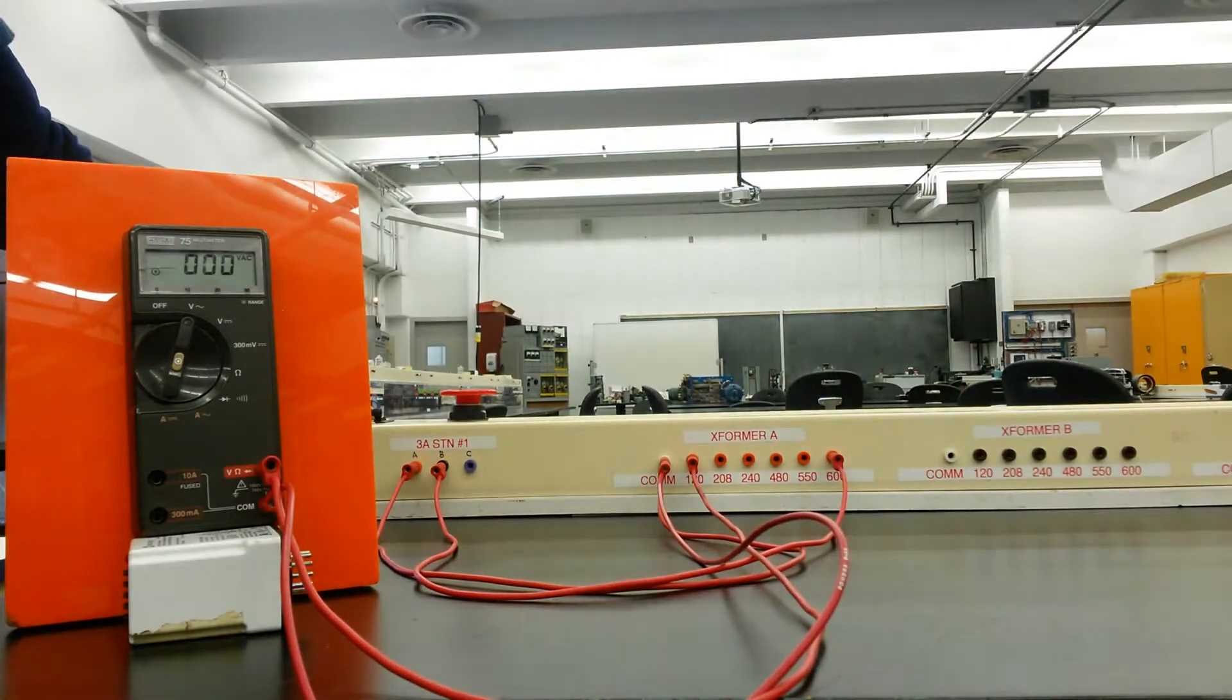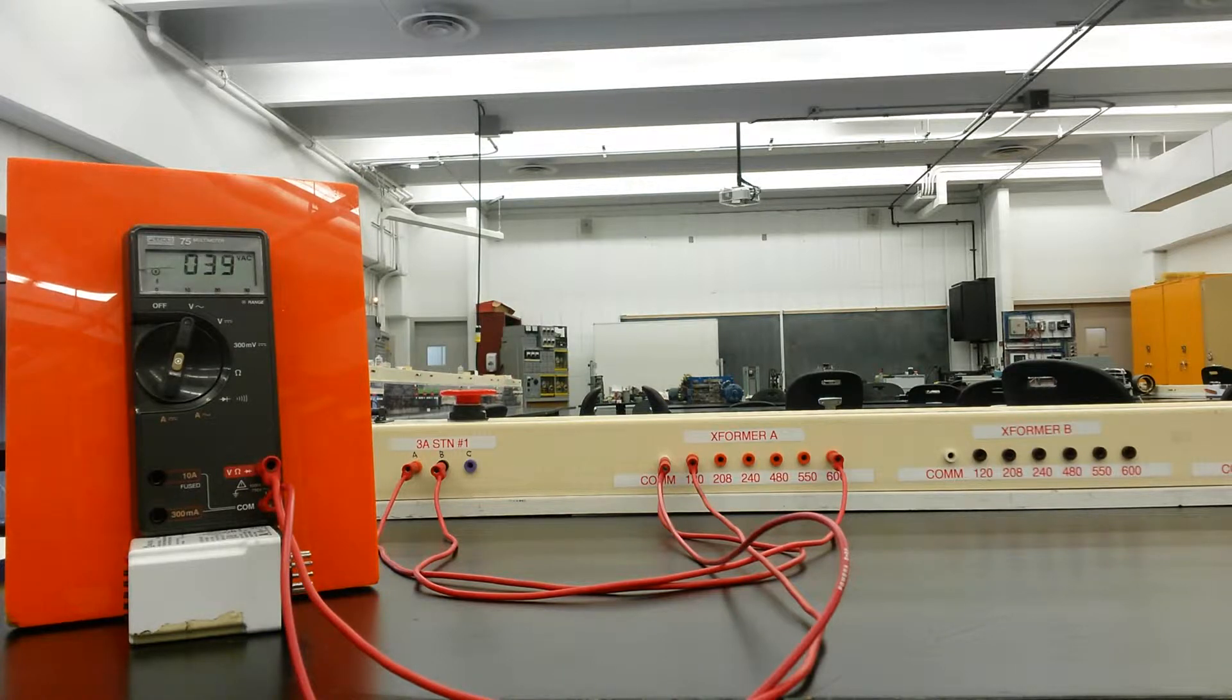If I put 2.8 into 600 volts, I've now changed everything and I only have now 40 volts available between the common and the 120, because I put 2.8 across a whole whack of turns between the common and the 600. I've changed the ratio of volts per turn for the entire transformer, and now I have a much lower voltage available between the common and the 120.